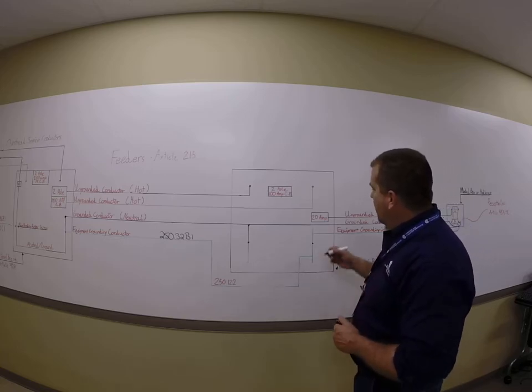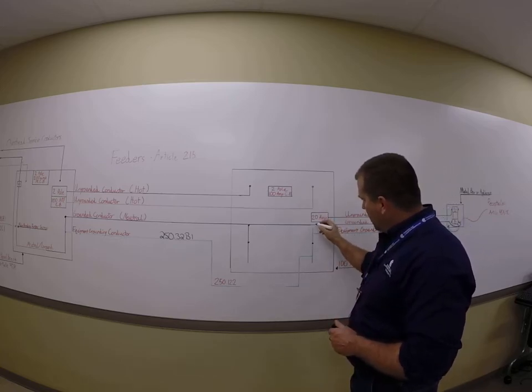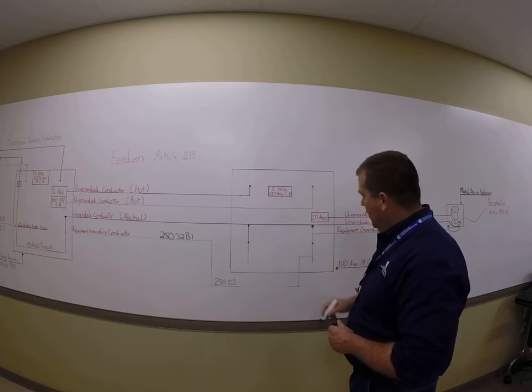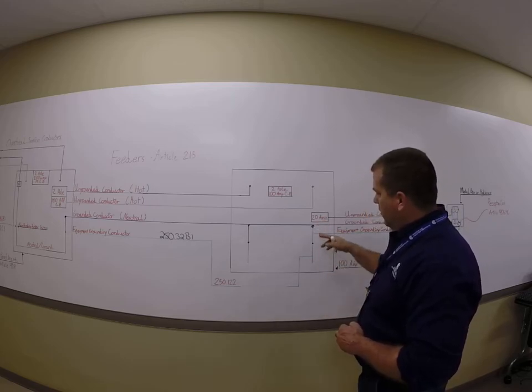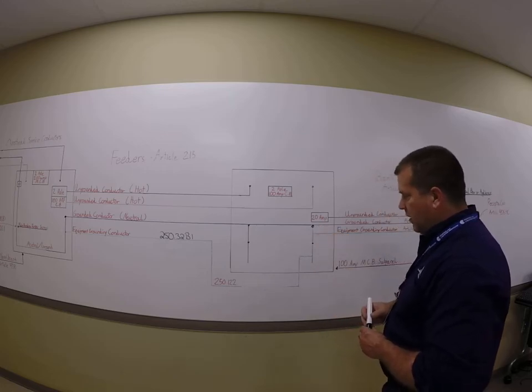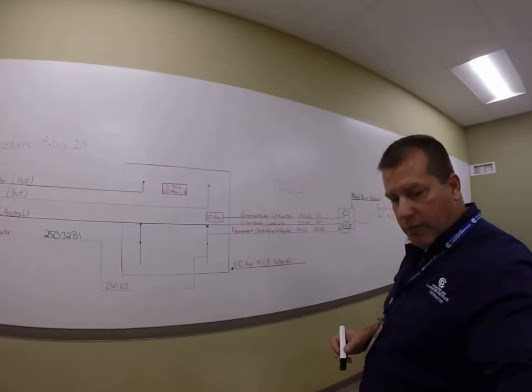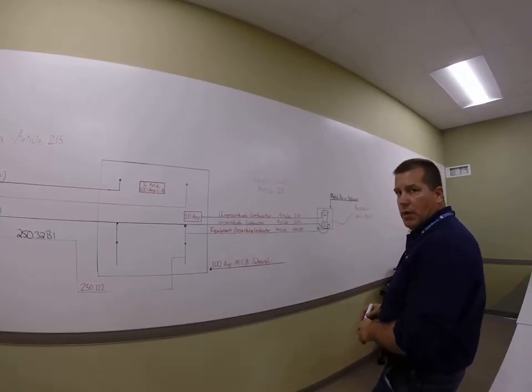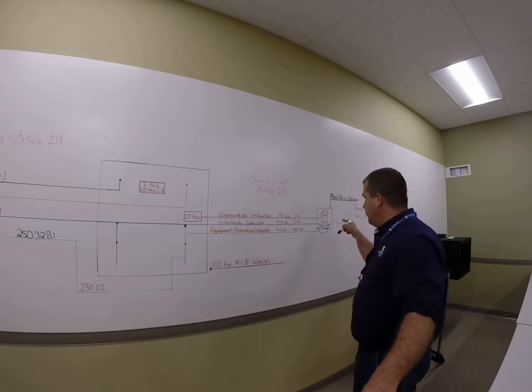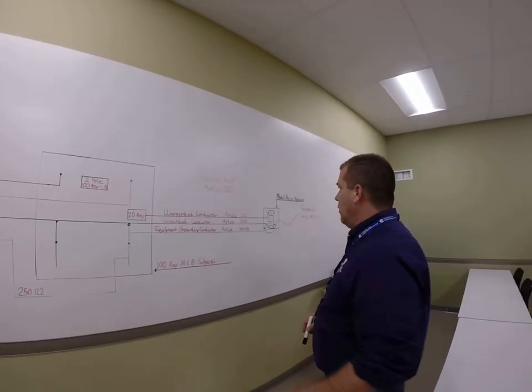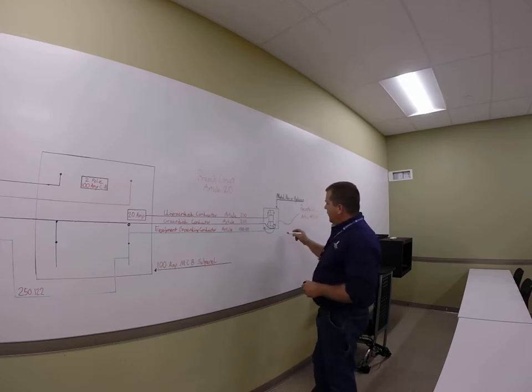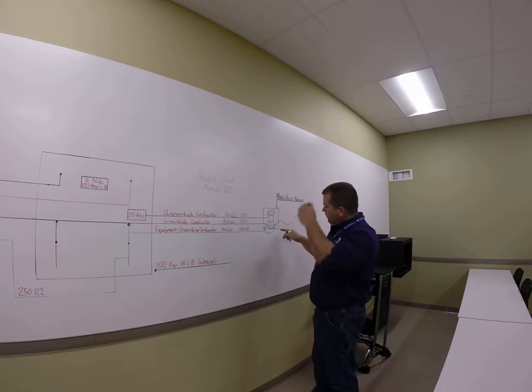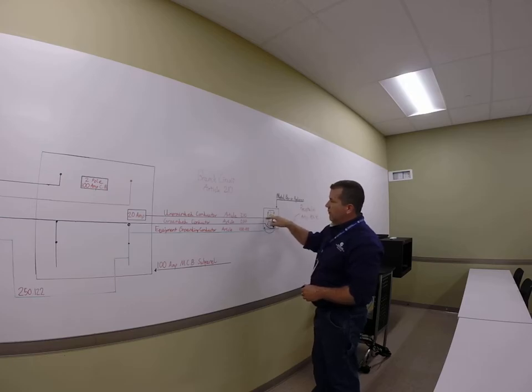They're going to come with the green screw. So let's just say I inadvertently, and I'm going to pretend that this is a green screw, I put the green screw and I connect my ground bar or my equipment grounding conductor to my neutral. Now watch what will happen here. So if I put my camera over and I pretend I have a load, over here I'm looking at me plugging into a receptacle. So if I plug into a receptacle, I'm all plugged in, everything's working.